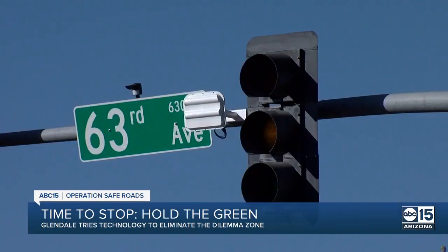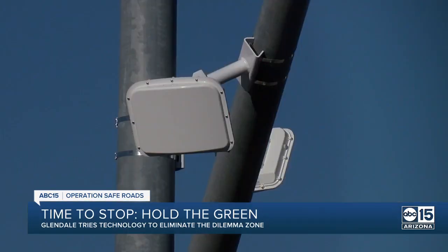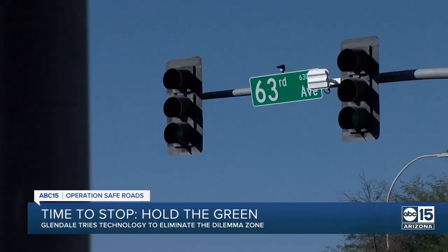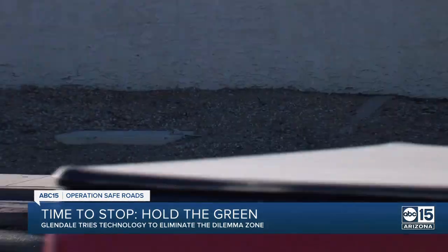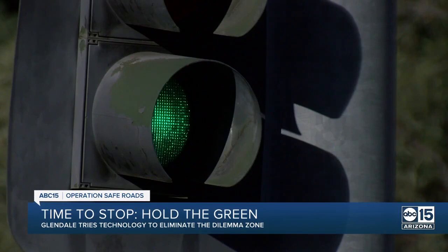But Glendale is trying to take the guesswork out of yellow lights with these Wavetronix continuous tracking advanced detectors at 63rd Avenue and Peoria. The sensors send out radar signals. This technology sees a vehicle as it's coming right through from when it enters the dilemma zone until it leaves, and it's making continuous calculations for the possibility of extending that green phase.